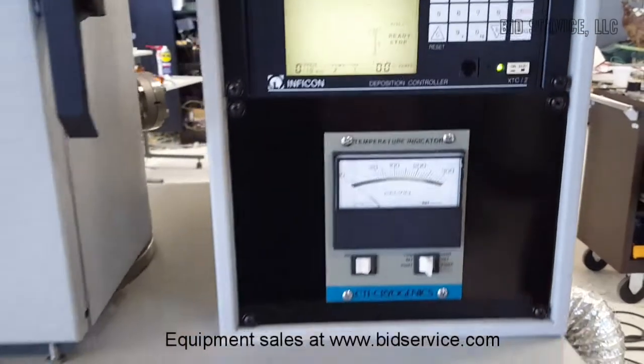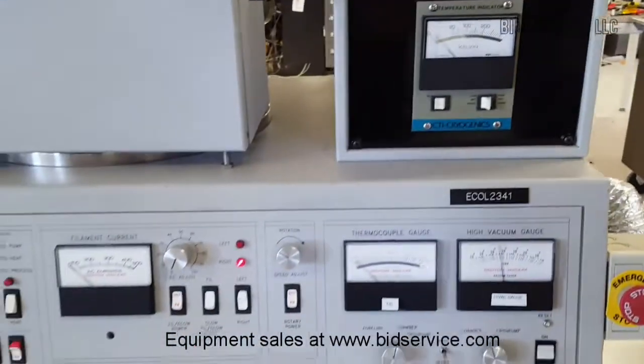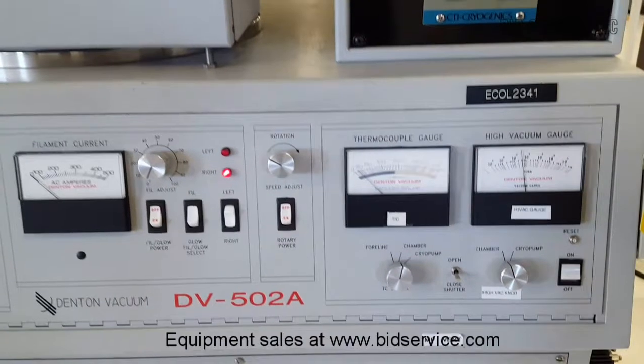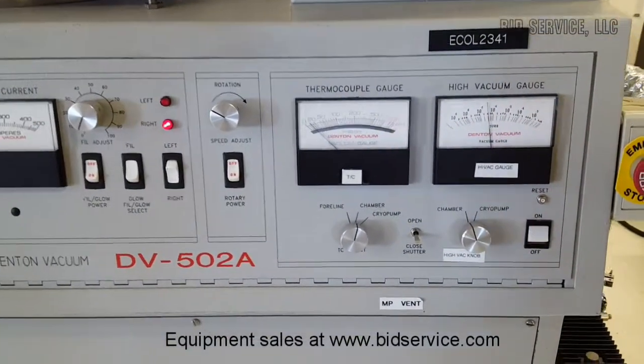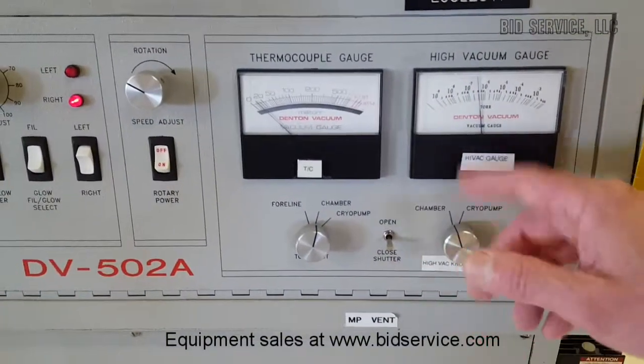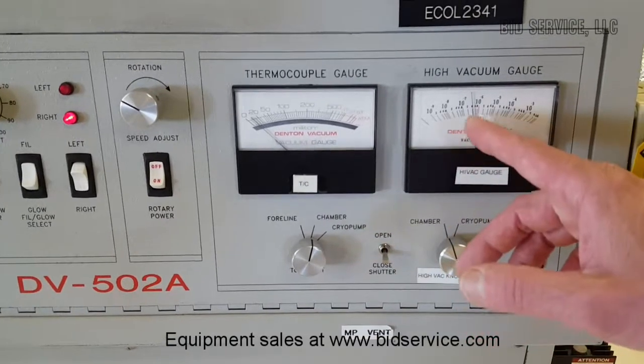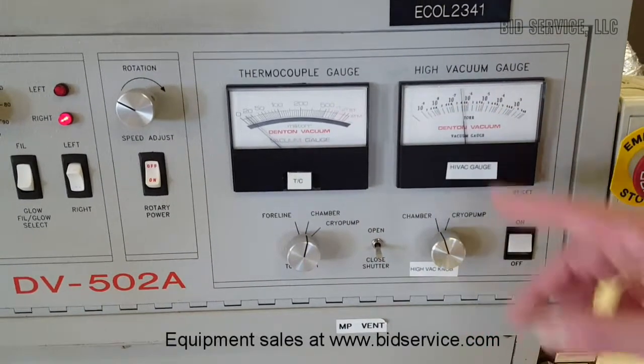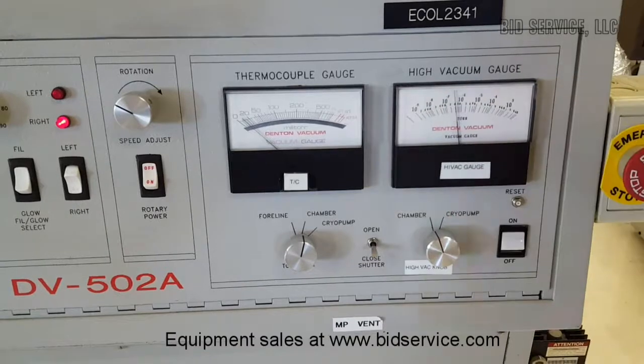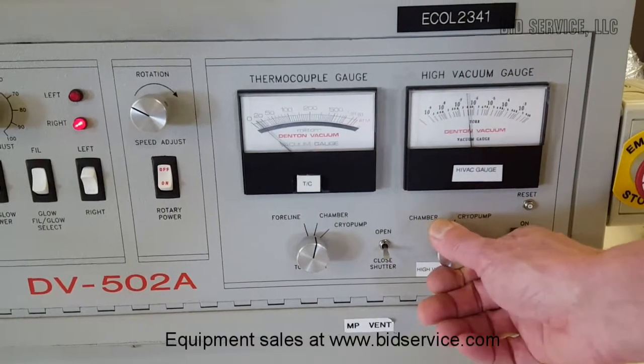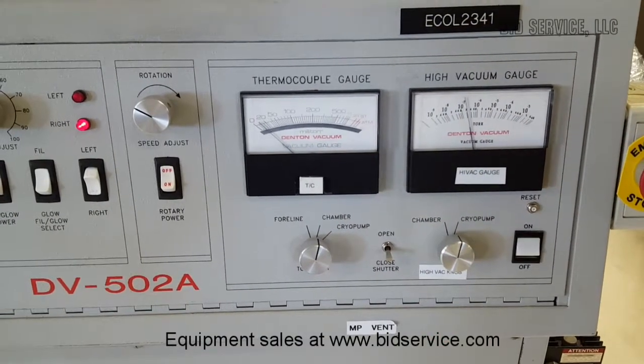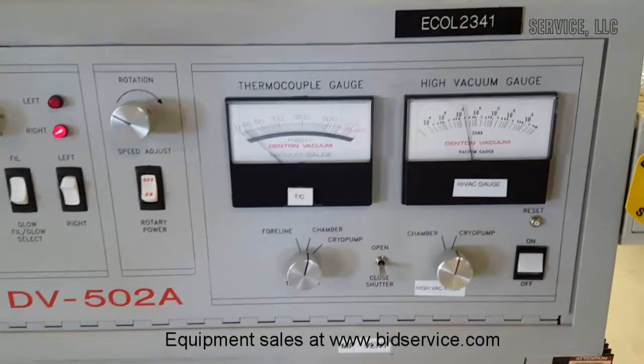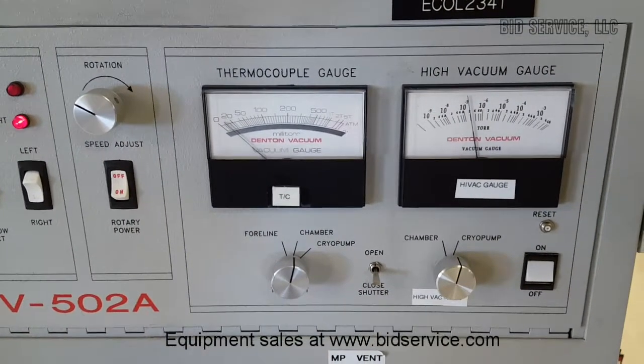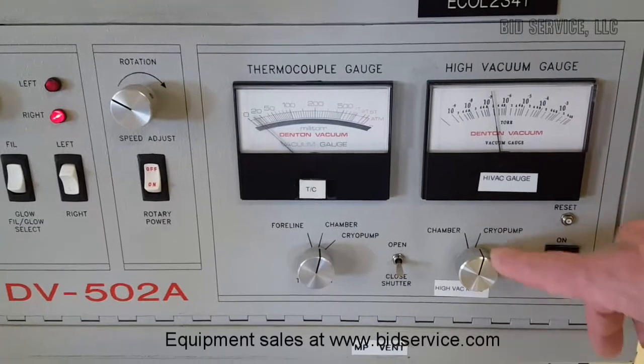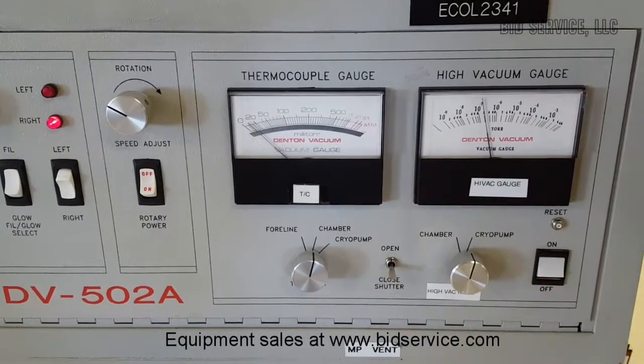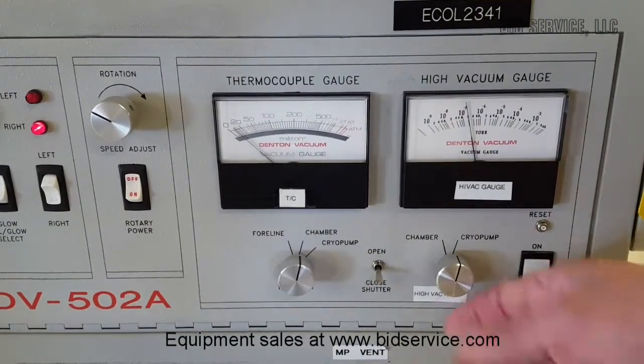And I have it under vacuum right now, reading the chamber. It's been lower than this. I've just had this open not too long ago. So the ultimate pressure on the chamber is less than 2 times 10 to the -7. And then you can also look at your cryo pump vacuum, and this will just go into the 8 range with the high vac valve closed.